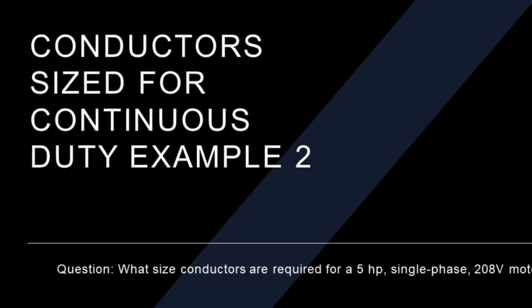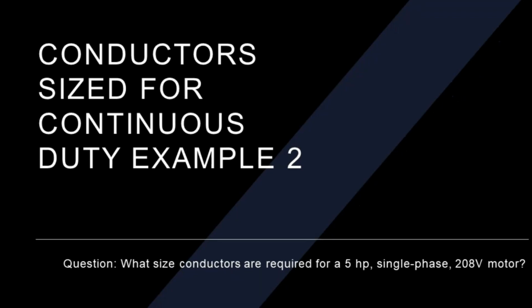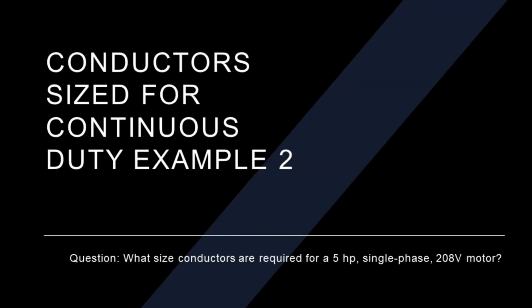Okay. Another example for conductors. Let's look here. What size conductors are required for a 5 horsepower single phase 208 volt motor? Okay, so I'm going to go to a single phase 208 volt motor. I'm going to take my time here, let you guys take a peek in your books, see which table you want to use for a single phase 208 volt. I hope that you guys landed on 430.248.